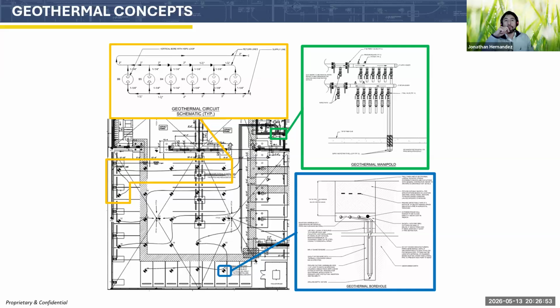Losing one borehole would provide that Christmas light issue - you lose one borehole, you lose that whole ambient loop. There are ambient loops; it's a different type of design, much larger pipe, a different type of purpose. That's not what these are, if you may have heard of those. These are circuits in a bore field.